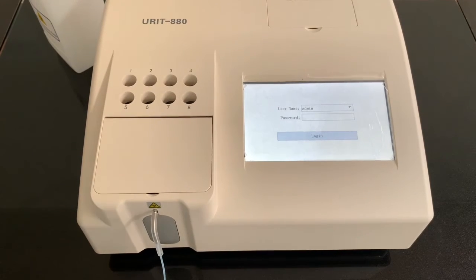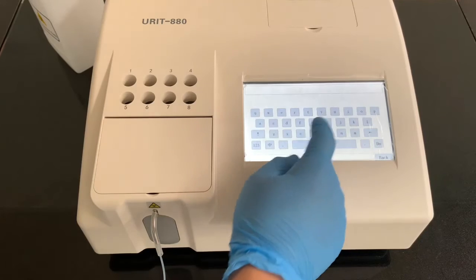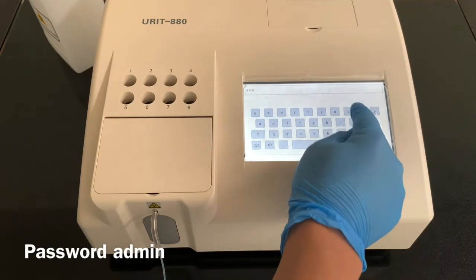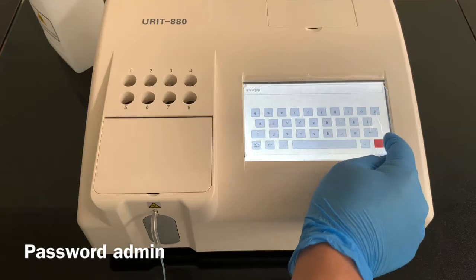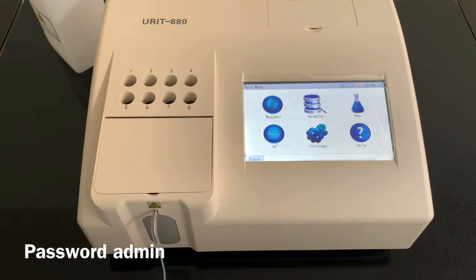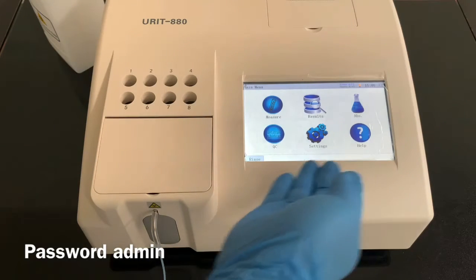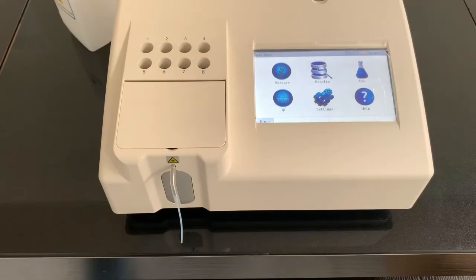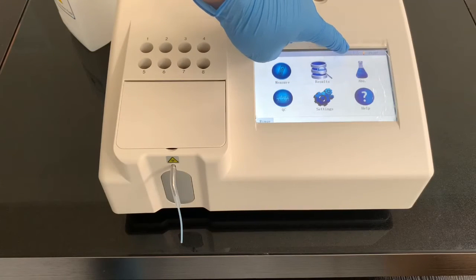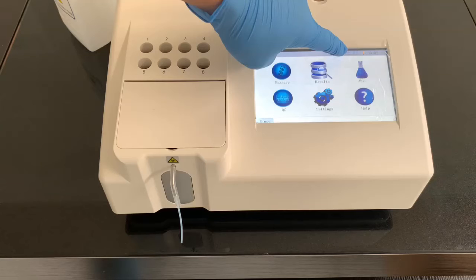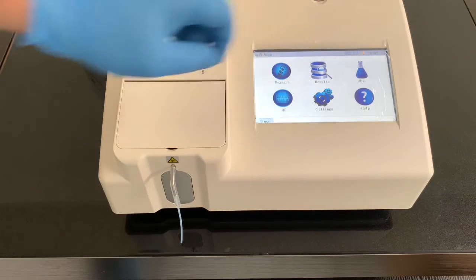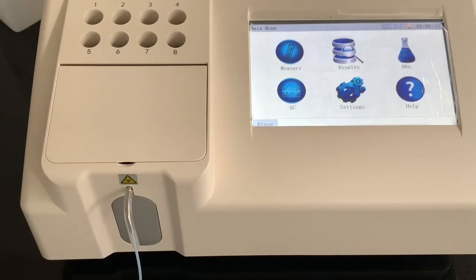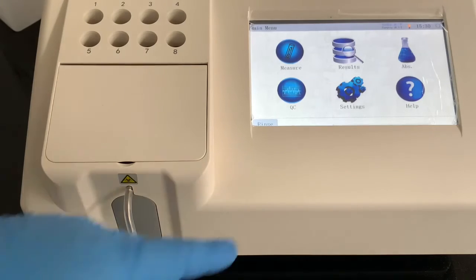To log in for the first time, the password is admin. After login, we will be able to see the main interface. After initialization, we need to wait until the cuvette reaches 37 degrees. Now the temperature already reached 37 degrees. We can proceed to the next step, the AD water blank, and save.